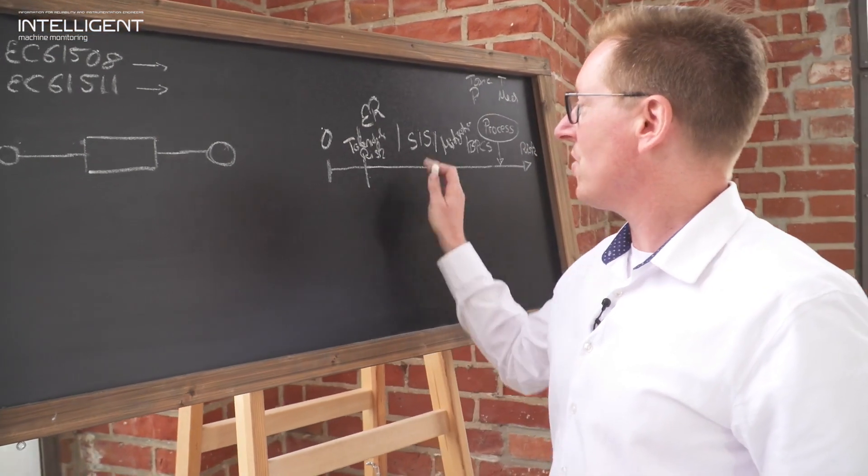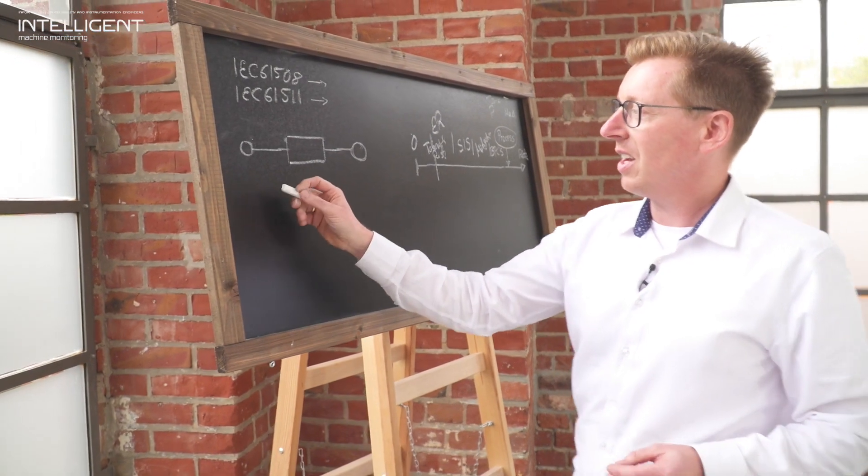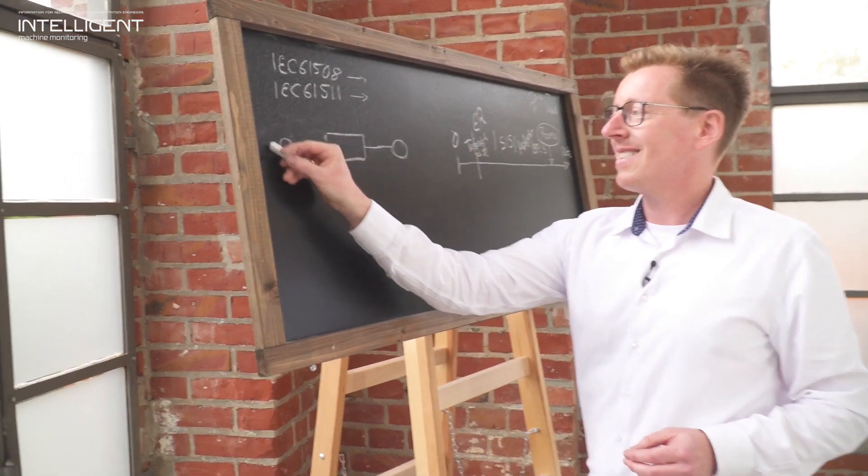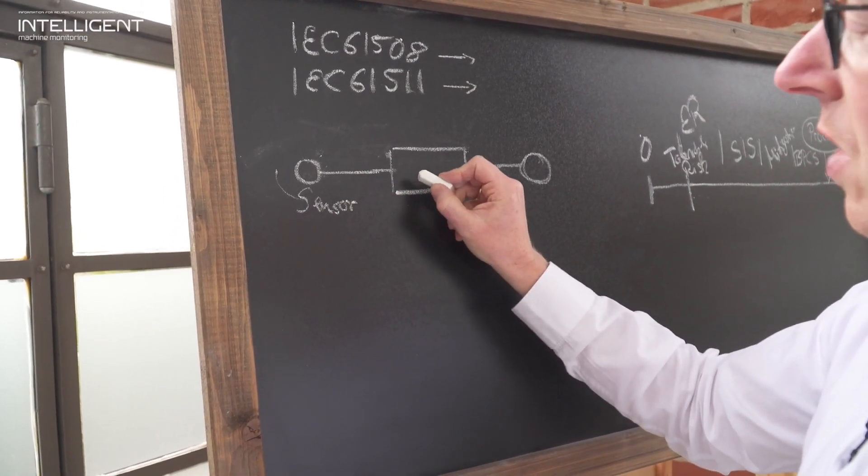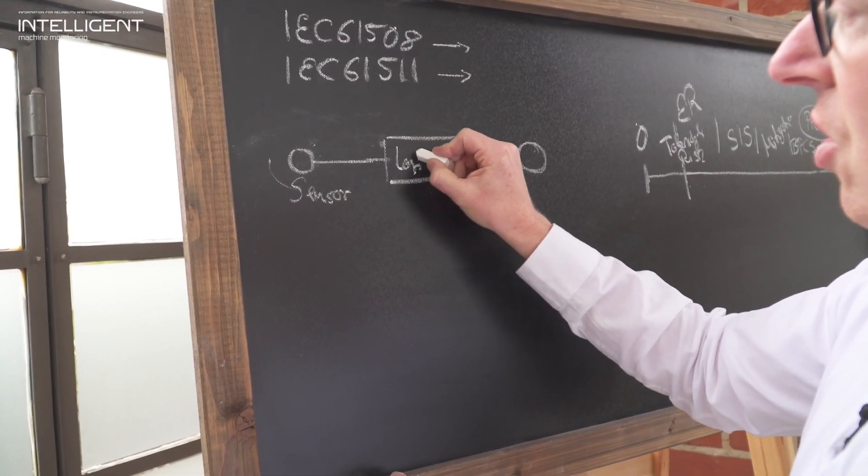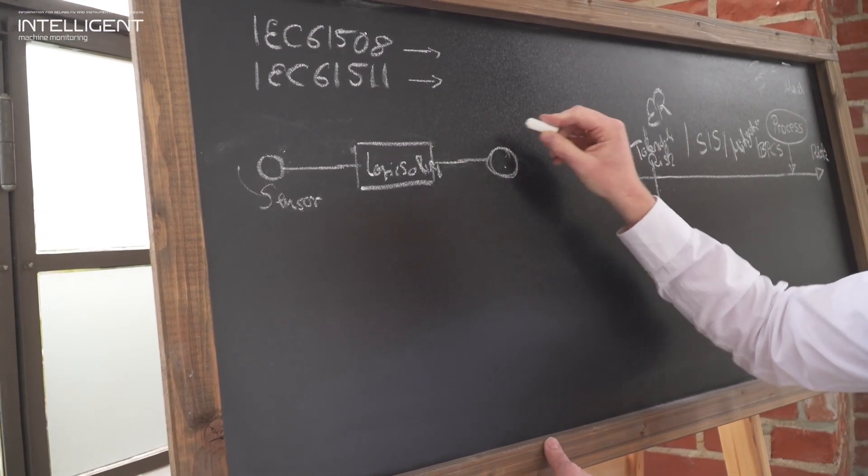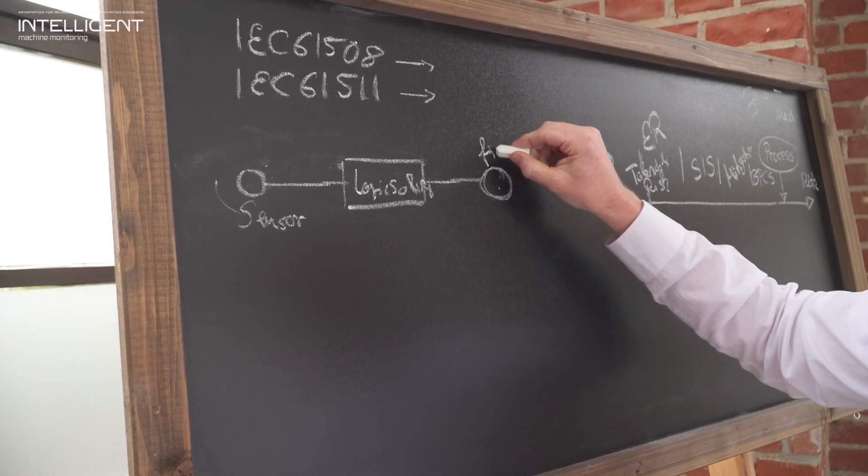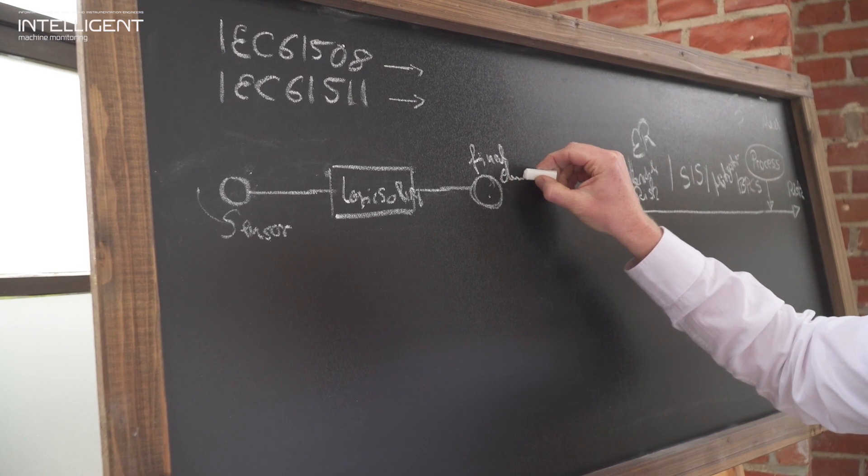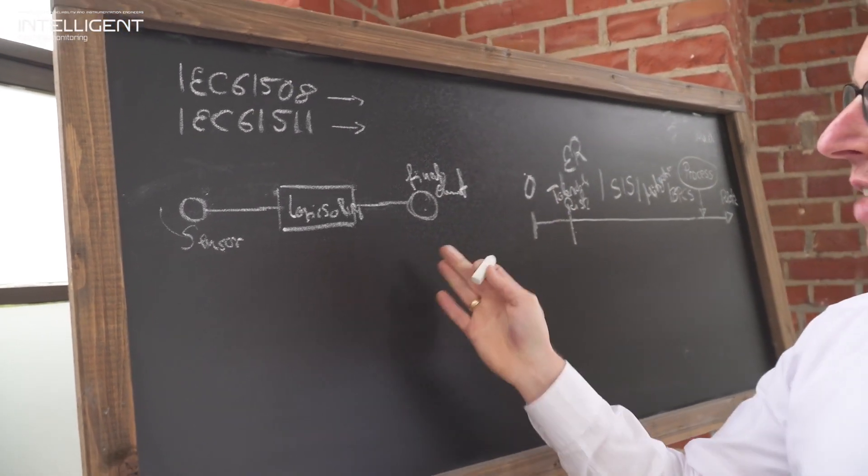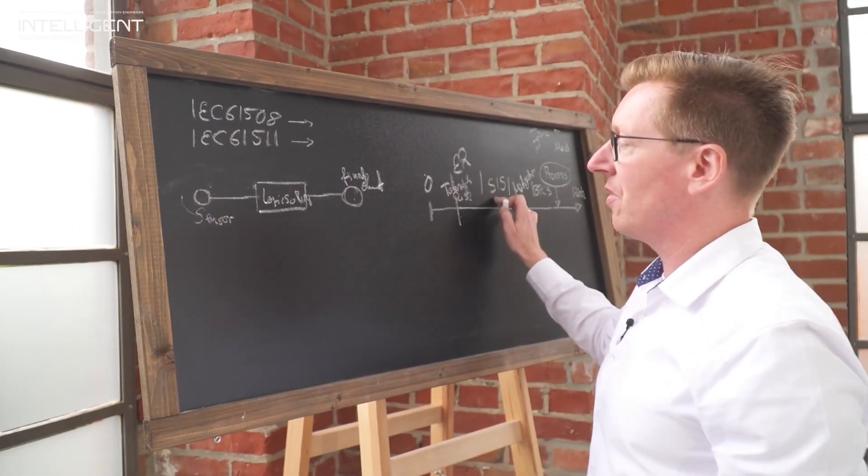In essence, every safety instrumented system consists of three components shown here. There is a sensor feeding a signal into a logic solver and there is a final element, a final actor. This could be your motor breaker, for example, on a rotating piece of equipment. And this in essence builds the core of a safety instrumented system.